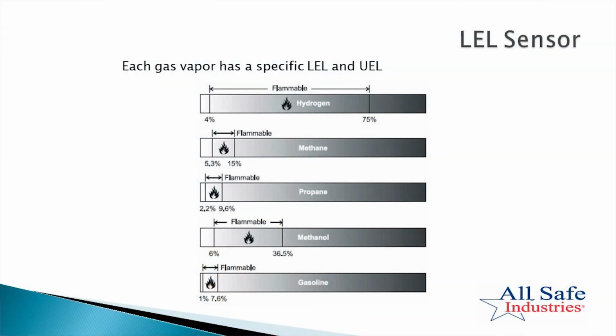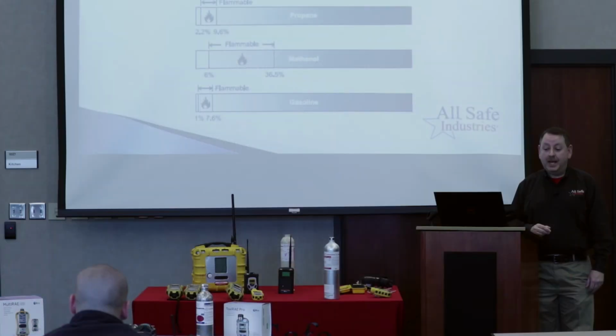Now we have the different flammable gases that you might run into, and each one has its own lower explosive limit and upper explosive limit. So the first example is hydrogen. And look at the wide band that exists for hydrogen. I don't think it's a surprise to anybody that hydrogen is a very flammable gas. It starts early and it stays for a long time. So 4% gas by volume is your lower explosive limit for hydrogen, and 75% is your upper explosive limit.